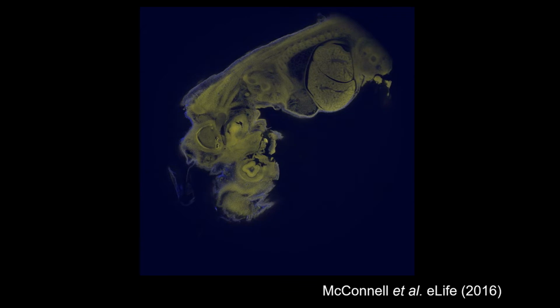Except this doesn't really show the resolution performance of the mesolens. So any zooming I'm showing you is entirely computational, where we've cropped at a region or we zoom in computationally. The mesolens is not a zoom lens, which means that we do have a fixed relationship between numerical aperture and magnification. They do not vary, unlike in the stereo zooms that you might find in your own labs or core facilities.